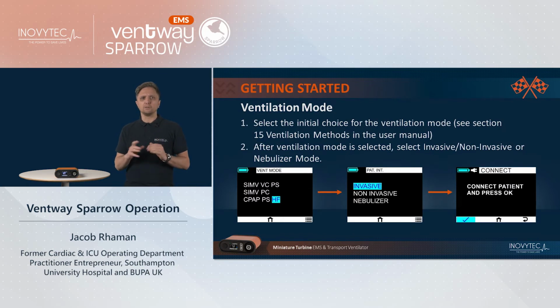Choosing the ventilation mode. Select the initial choice of the ventilation mode. This can be either SIMV VC, SIMV PC, or CPAP PS. After ventilation mode is selected, select invasive or non-invasive or nebulizer as a form of ventilation. You will then be prompted to connect the patient and press OK to start the ventilator.